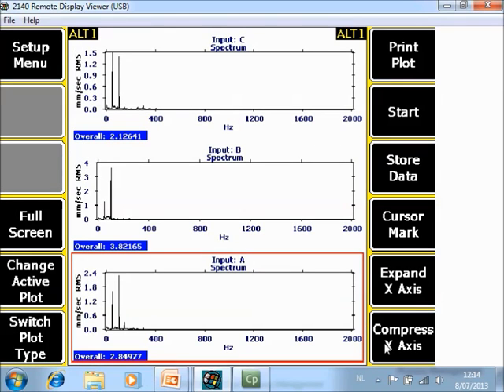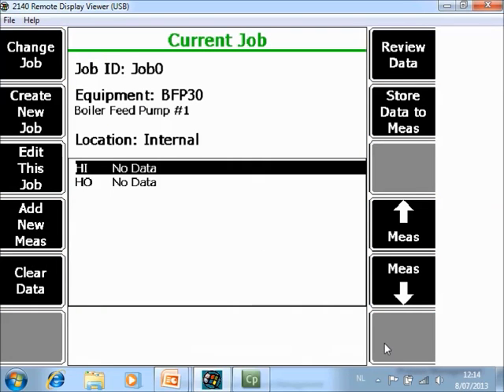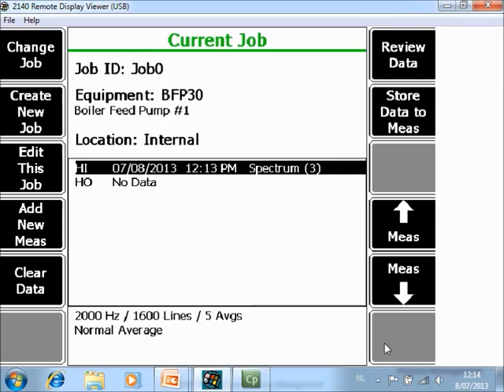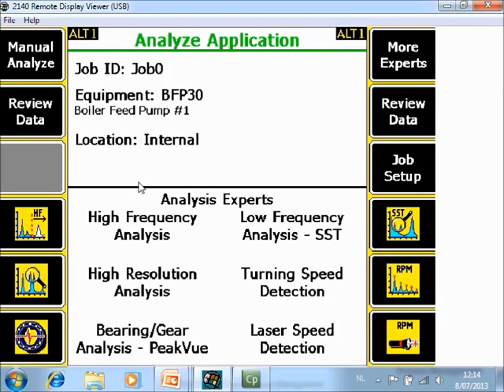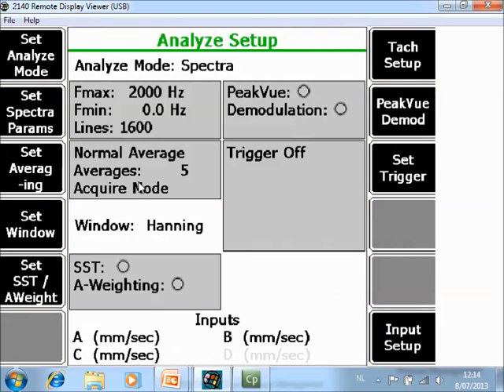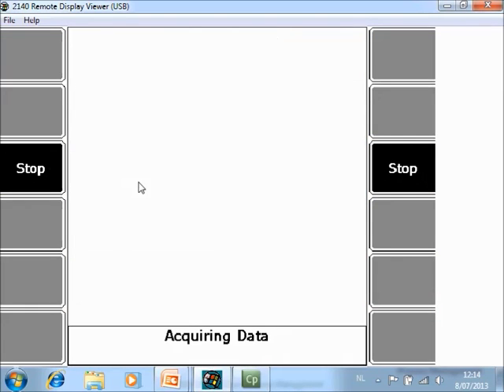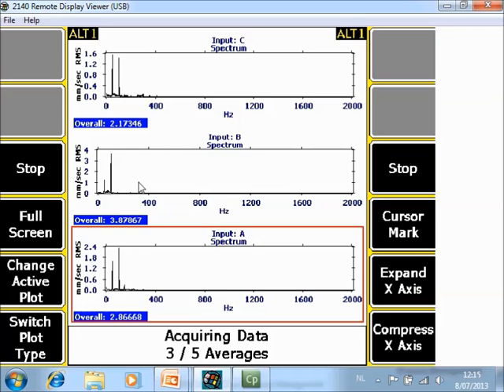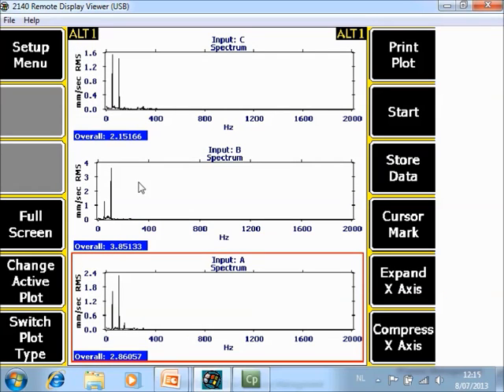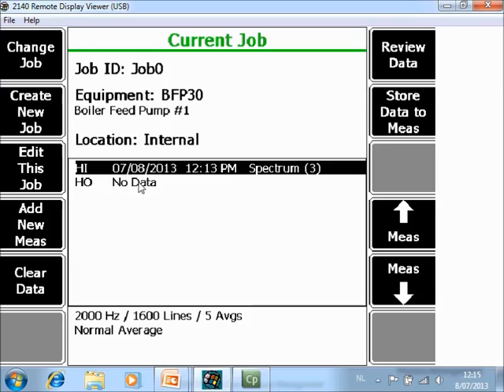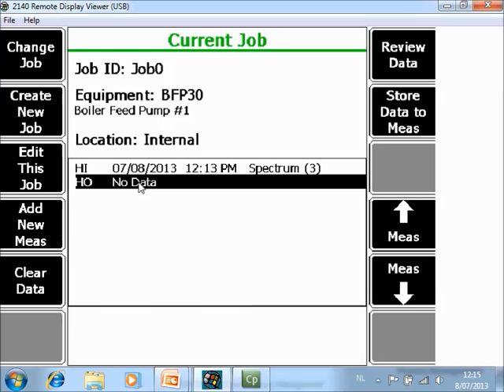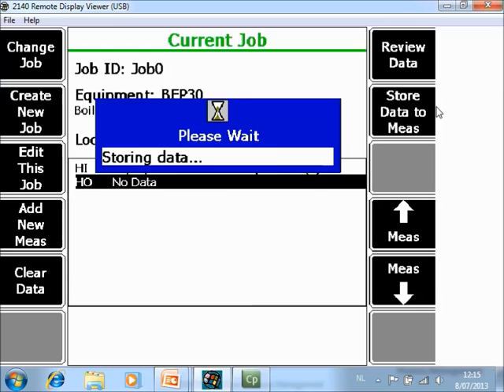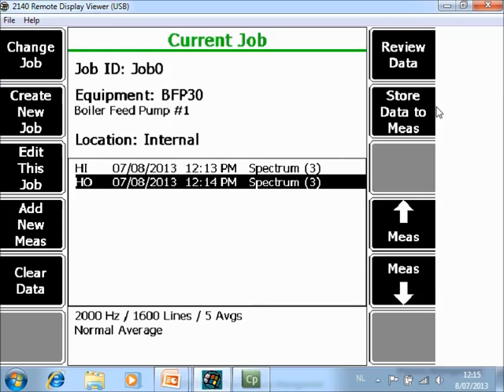After data collection, I go to F9 store data. And this was the inboard. So now F8 store data to measurement point. And as you can see, the three spectra are stored here. Now I move the sensors to the outboard location and I retake data, the same setup. And I also can store it now. Store data to outboard, store data to measurement point F8. And the data is stored.